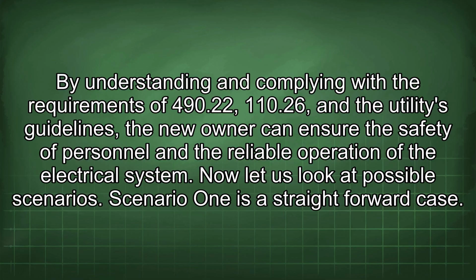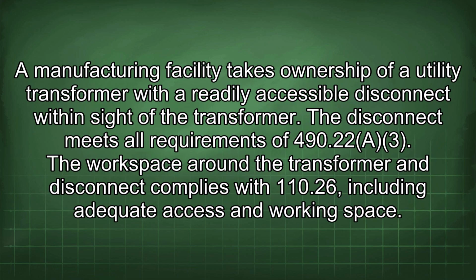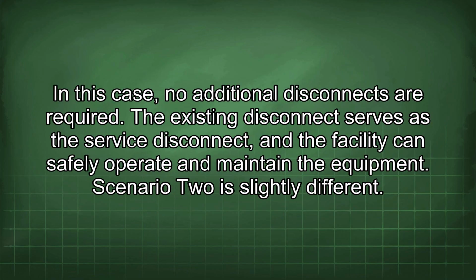Now let us look at possible scenarios. Scenario 1 is a straightforward case. A manufacturing facility takes ownership of a utility transformer with a readily accessible disconnect within sight of the transformer. The disconnect meets all requirements of 490.22. The workspace around the transformer and disconnect complies with 110.26, including adequate access and working space. In this case, no additional disconnects are required. The existing disconnect serves as the service disconnect, and the facility can safely operate and maintain the equipment.